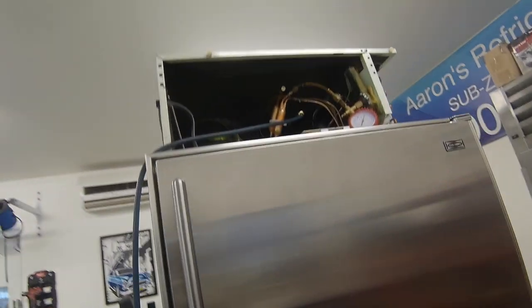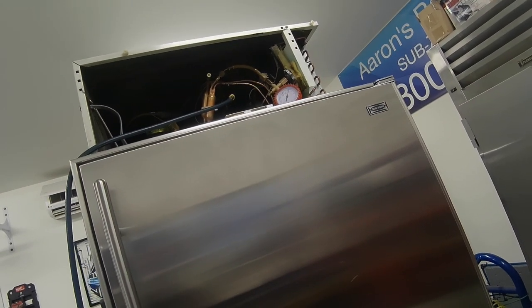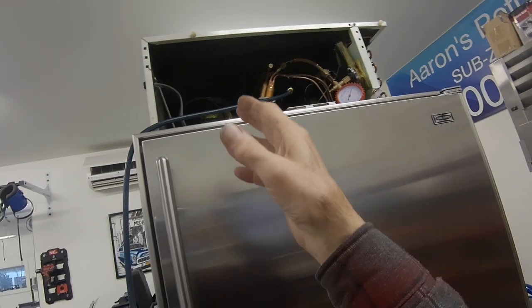Let's see how long it takes, because I've done this before and the pressure went all the way up to about 65, which is probably equivalent to what the pressure should be at room temperature here. So there's several things we can do here. If it is a restriction, we can just pop it up a little bit more. We can change the heat exchanger, this is a normal fix, this is normally what we would do. But since the refrigerator is in the shop, we're not in the field, we could try something else. Now I do have a video on my channel on how to clear a cap tube using lacquer thinner, a little bit of lacquer thinner, suck it through, cut drain. First thing we're going to do is we're going to pull out whatever refrigerant we have in there. Nothing comes out and we know we have a leak because I put freon in here.